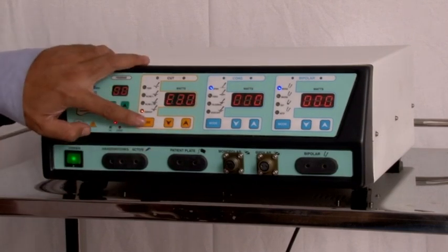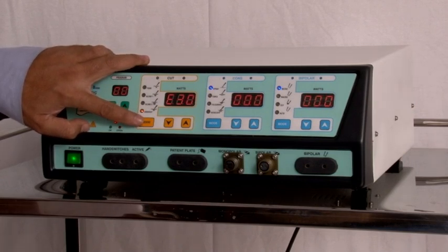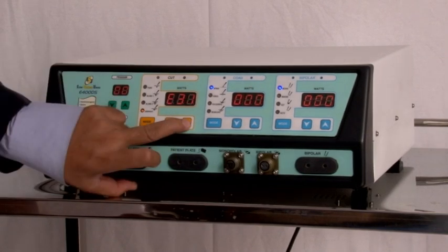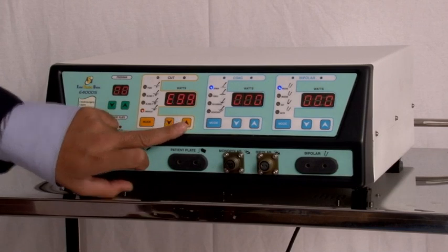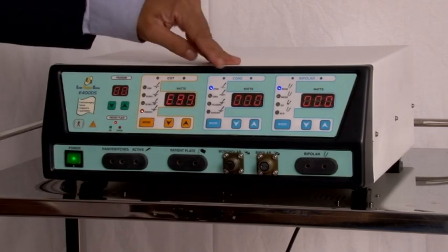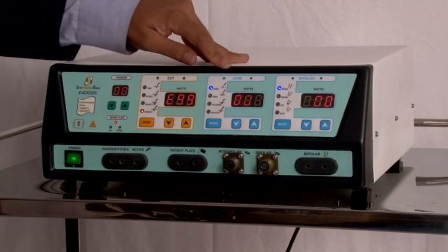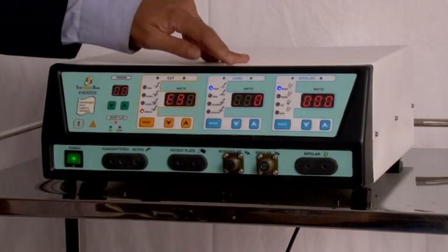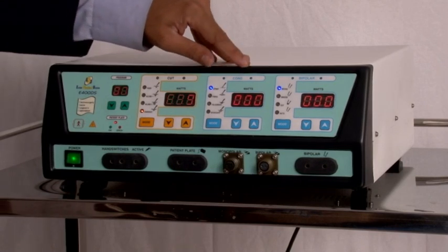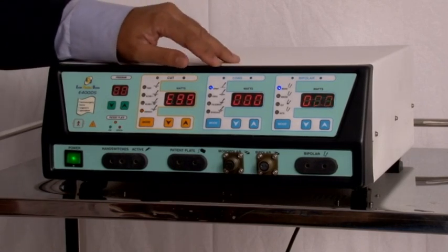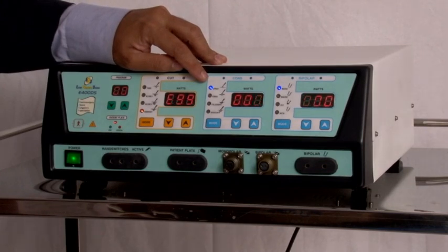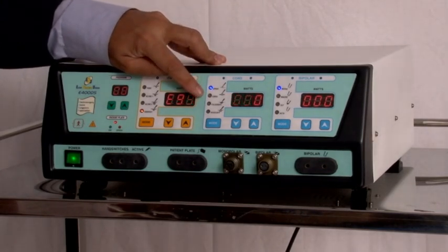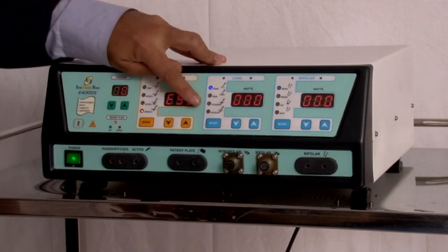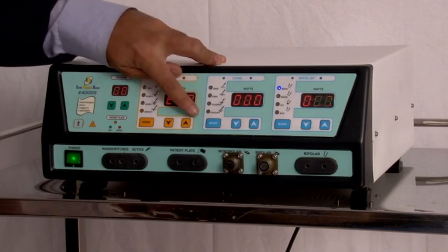Last mode in cutting is endo cut, with alternating intervals of software controlled cutting, useful in procedures like ERCP. Endo cut has a maximum power output of 99% of 300 watts. Other mode in monopolar output is coagulation, normally known as coag. In coag, we have four different types of output: spray coag, forced coag, fulguration and desiccation.